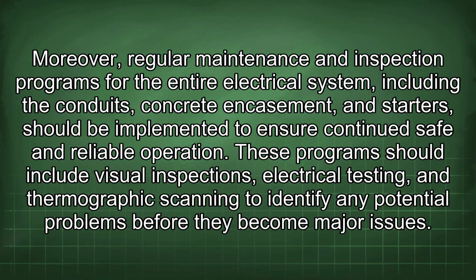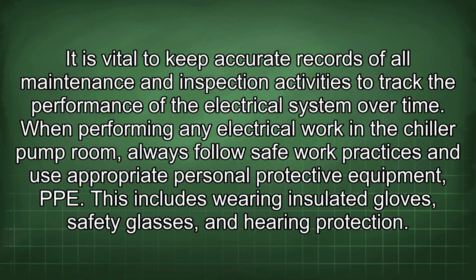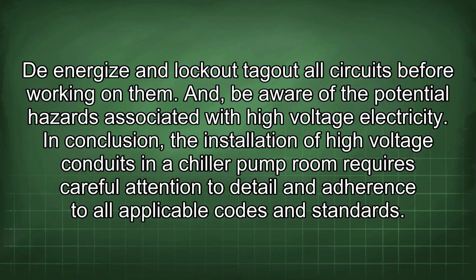These programs should include visual inspections, electrical testing, and thermographic scanning to identify any potential problems before they become major issues. It is vital to keep accurate records of all maintenance and inspection activities to track the performance of the electrical system over time. When performing any electrical work in the chiller pump room, always follow safe work practices and use appropriate personal protective equipment, PPE. This includes wearing insulated gloves, safety glasses, and hearing protection. De-energize and lock out, tag out all circuits before working on them, and be aware of the potential hazards associated with high-voltage electricity.